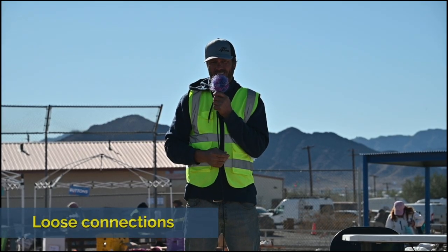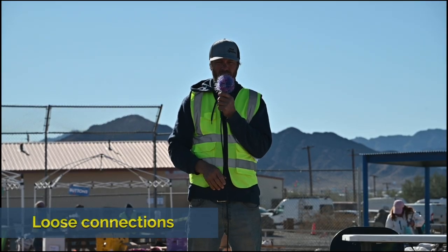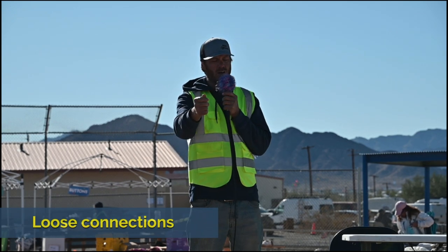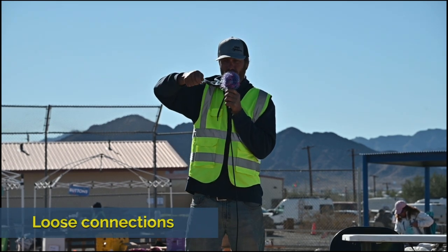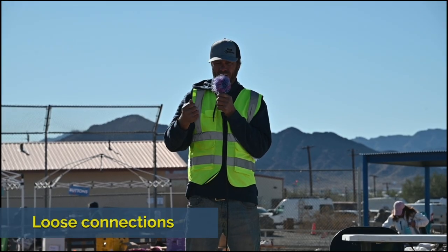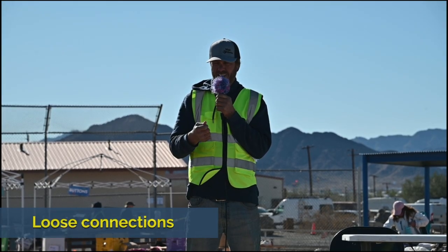I hate when I get to a system, and they're like, oh, I need to change this out. And I'm like, okay, I'm cool, I'm changing it out. And I go to grab the wires to hold it while I'm unscrewing them, and they just come out of the bottom of the charge controller. And I'm like, right on, I just saved this person possibly some headache.